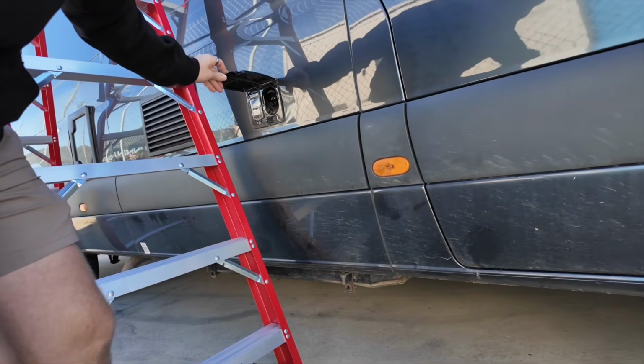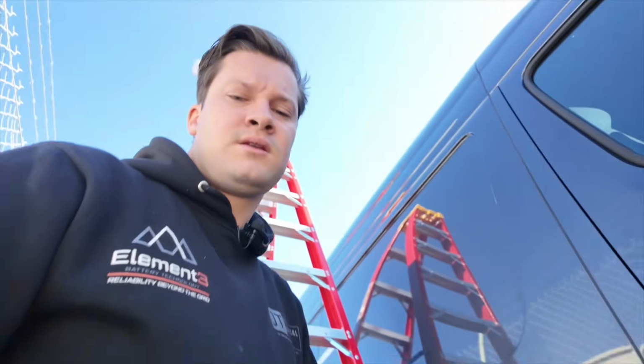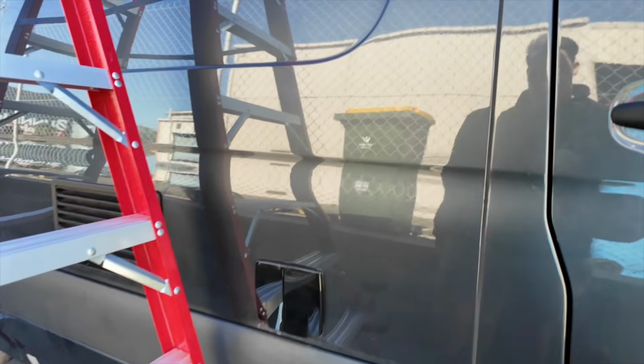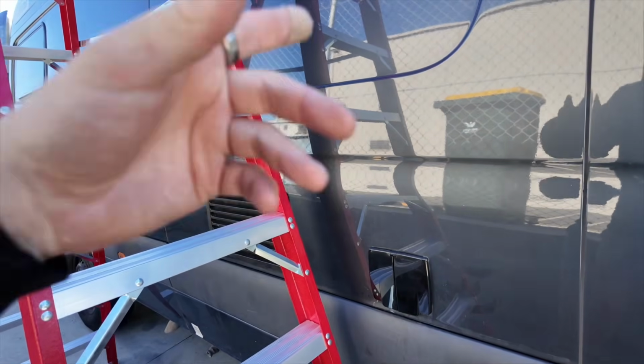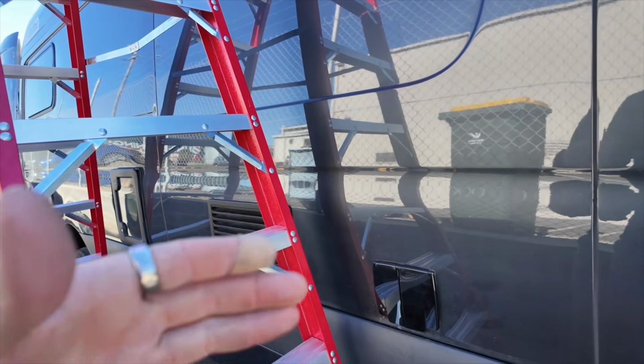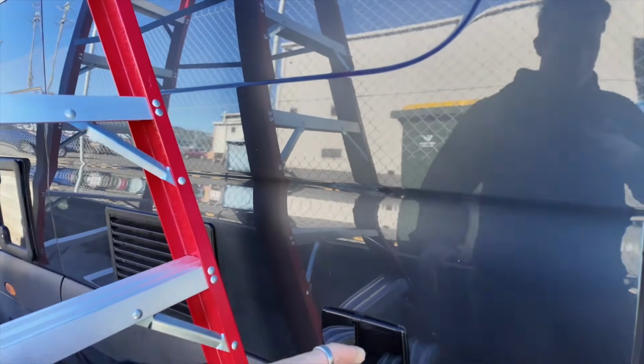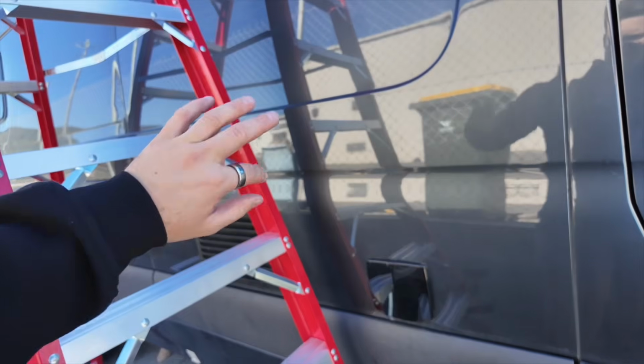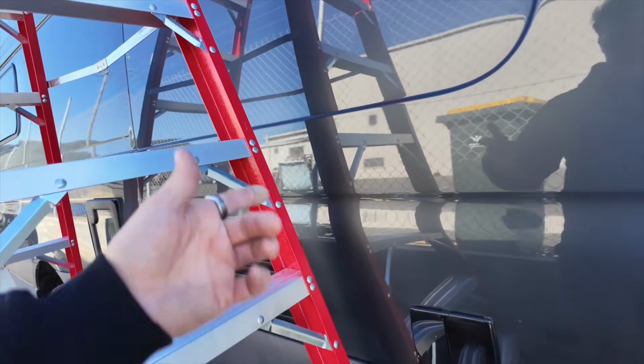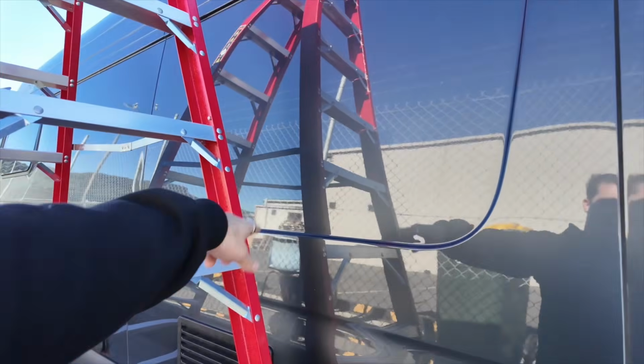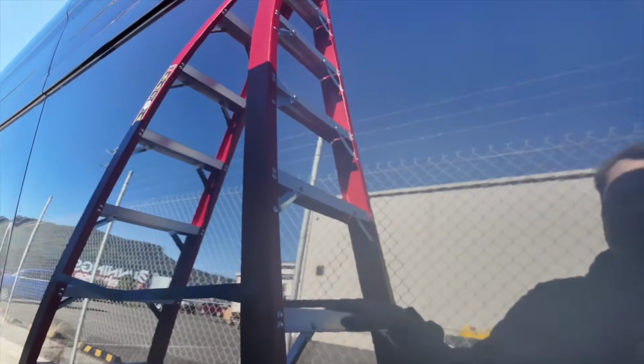You've got your 240 inlet here. Now some people ask, why do you have 2 AC input circuit breakers? It's because of the way the thing was originally wired - there was one power point on the input-only side, which would have been outside of our input protection given how the wiring was configured. So we added the AC input circuit breaker inside to protect this extra power point.